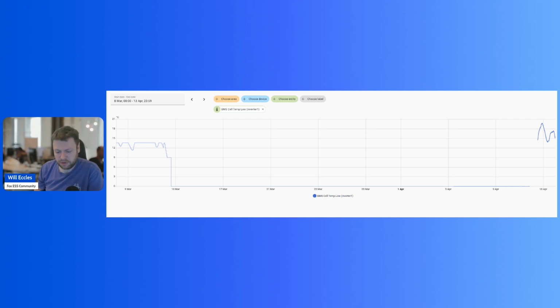I wanted to record a video to explain that this fault is normal and can happen. We see it pop up quite a lot going through winter in the UK, especially for batteries that don't have heaters or are exposed outdoors or in outbuilding-type environments without heating. So that error message has legitimate use cases, but not during spring in the UK, and not on just one battery.